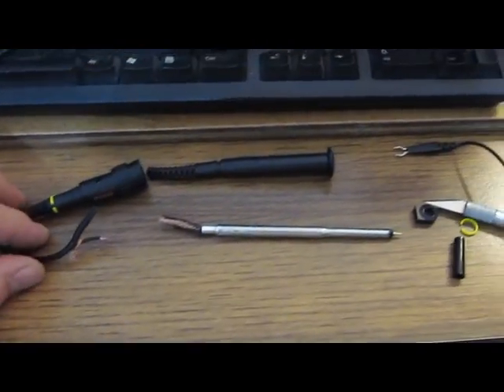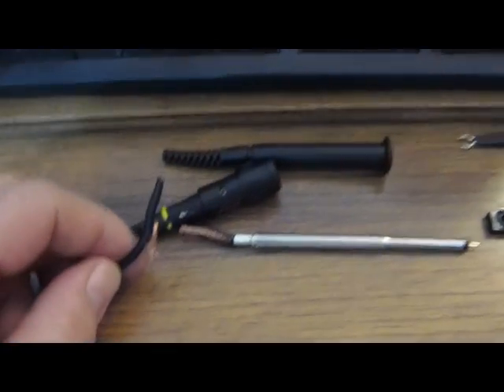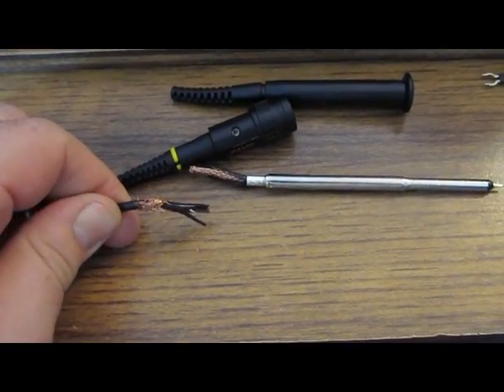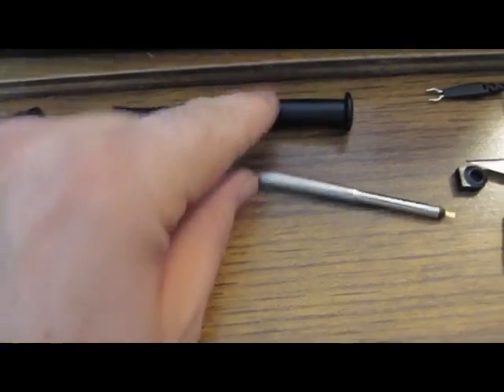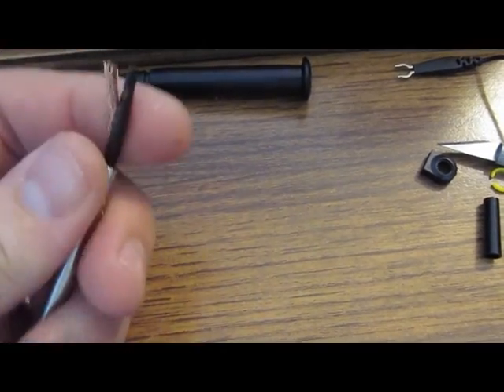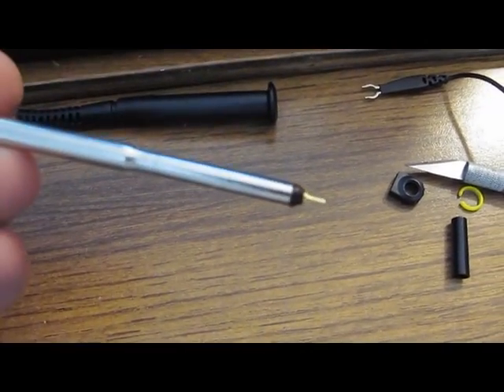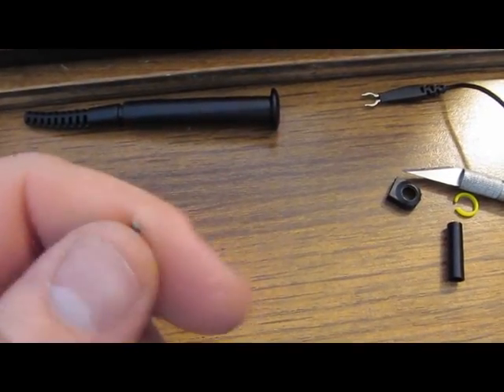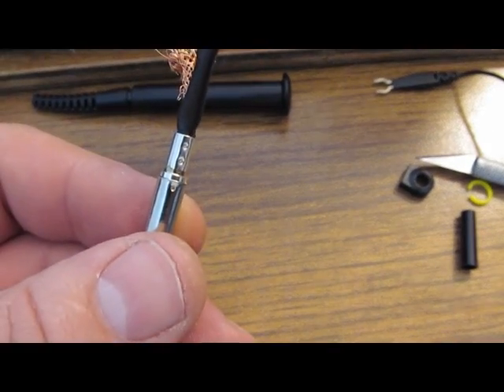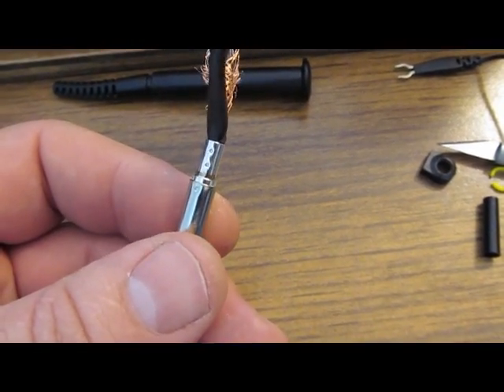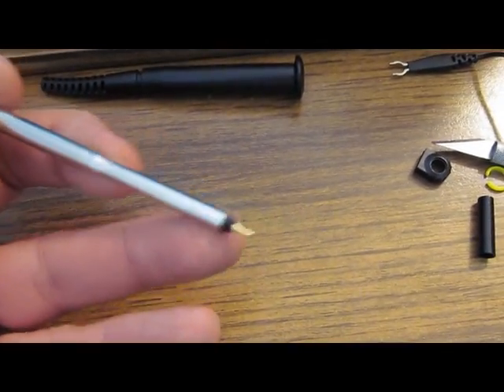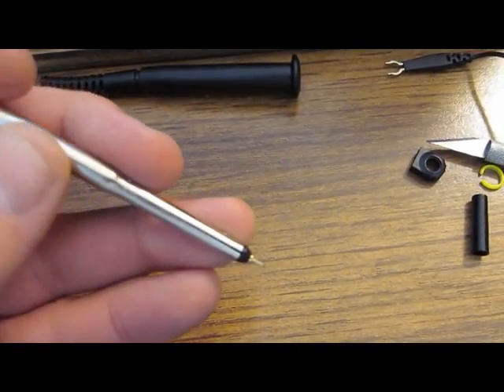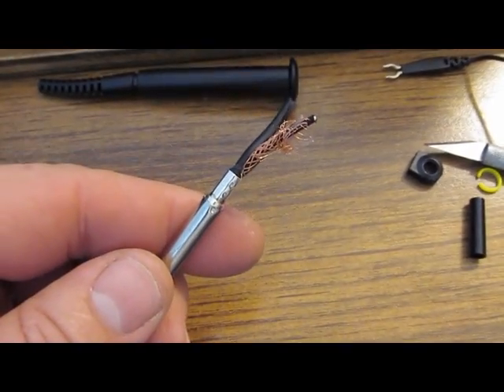So I started taking the probe here apart. Snipped off the coax towards the end of the tip here. The coax in the end here seems fine. Whatever it is, it's up in the head here. You ohm this out and this is an open from the tip to the center of the coax. You can see here it's kind of a crimped, maybe a spot welded joint. It's hard to say. I guess the tip here may be press fit. I'll pull this apart and let's see what it looks like.